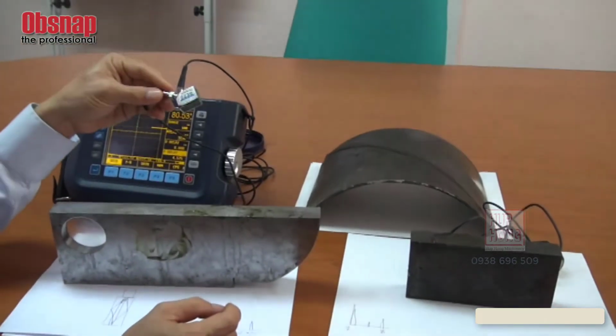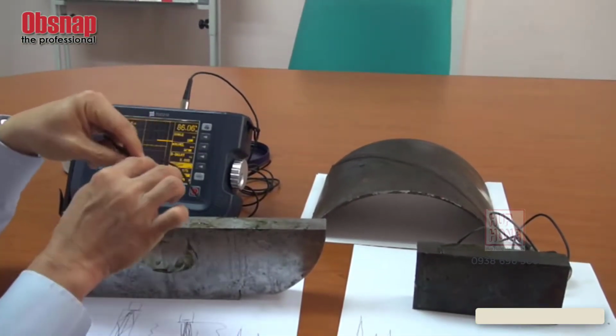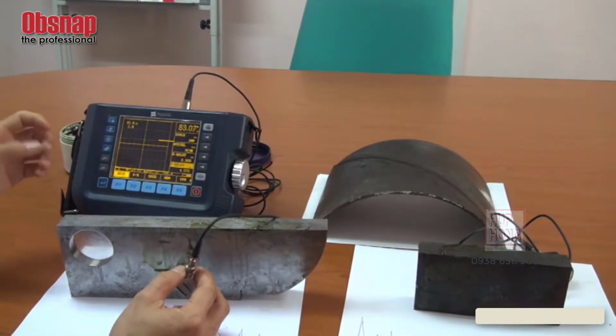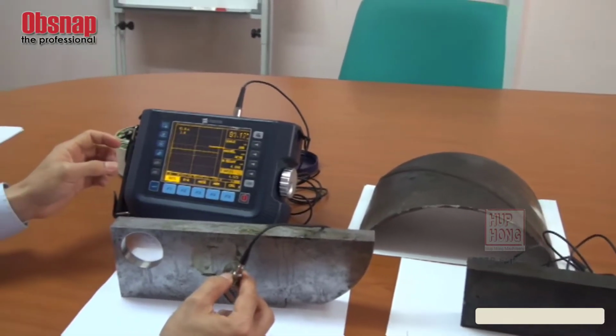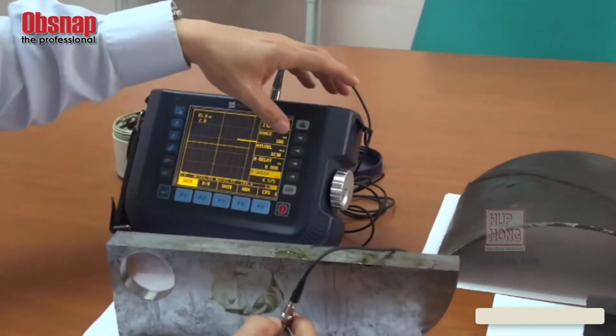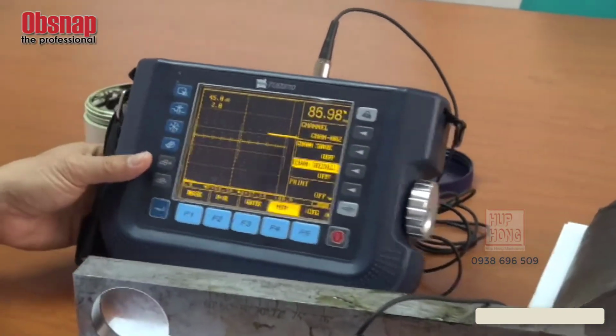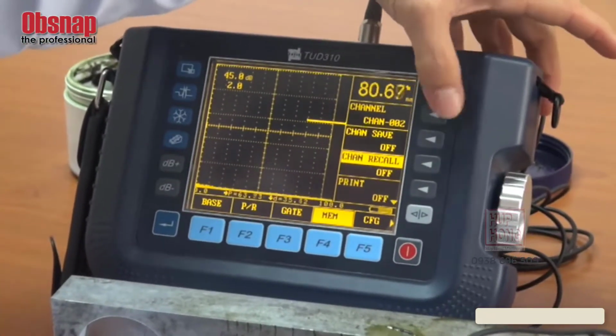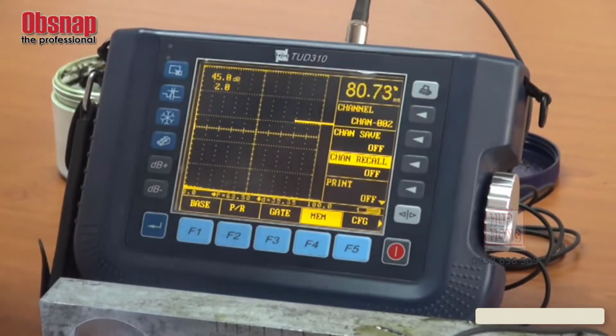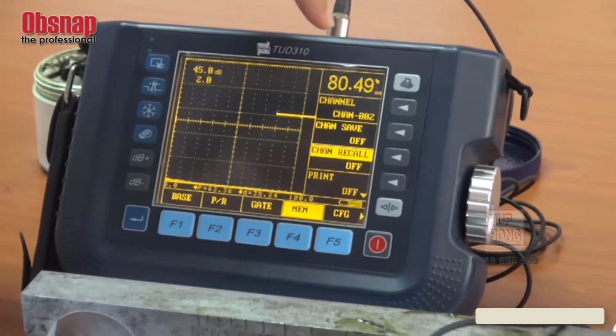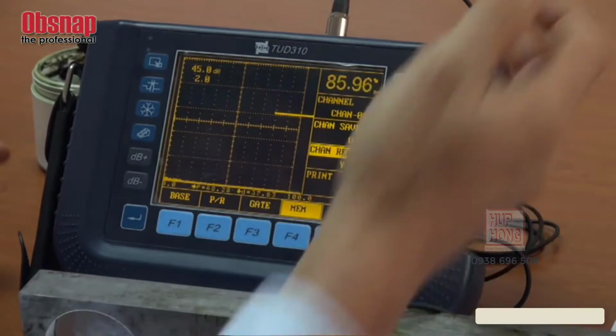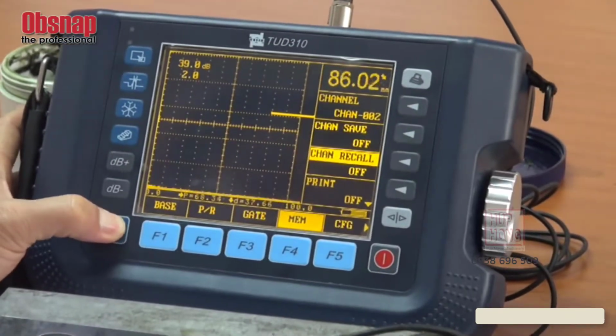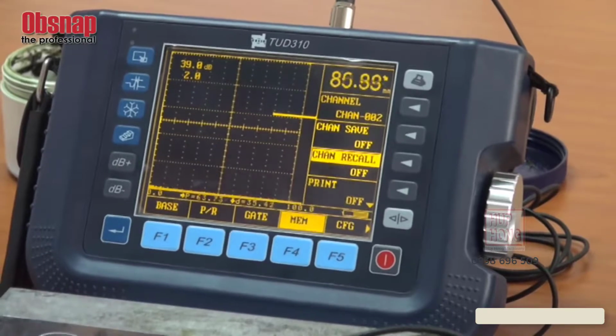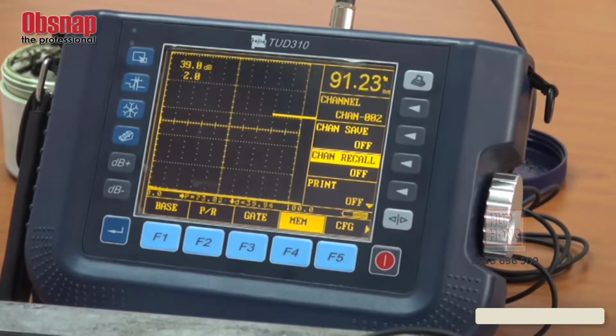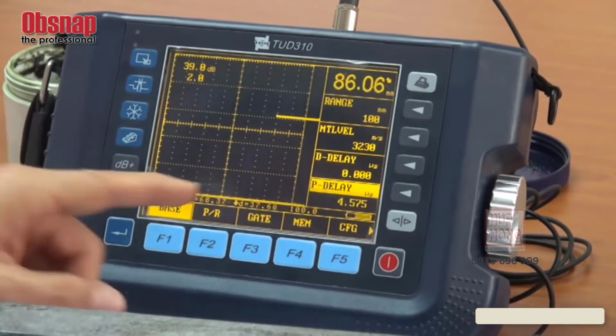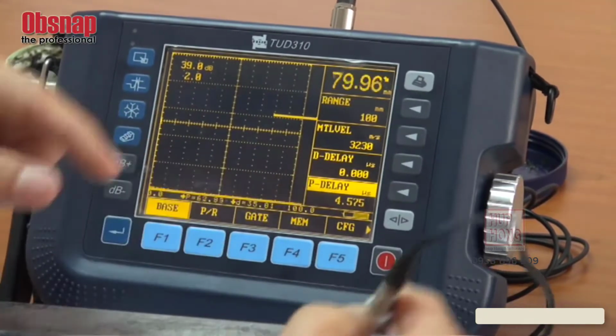We now change to this angle probe. As I said, we will need to recall the setting, because previously I have calibrated, and the way we recall it is by pressing memory, then we go to this channel. I remember I saved the setting at channel number 2. So in order to recall, I just turn to yes and no, then press yes. So I have successfully recalled the setting.